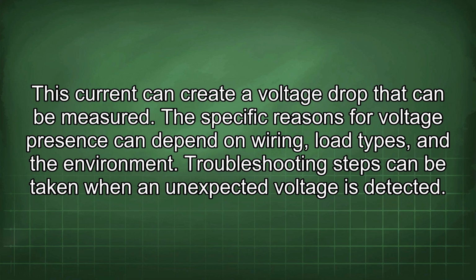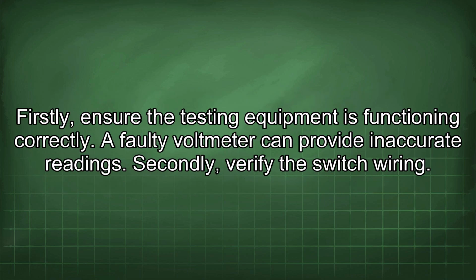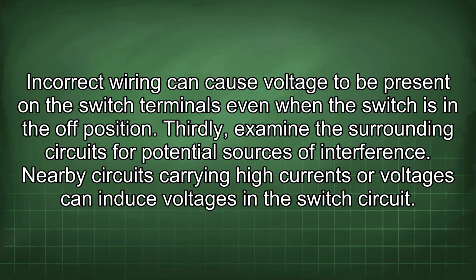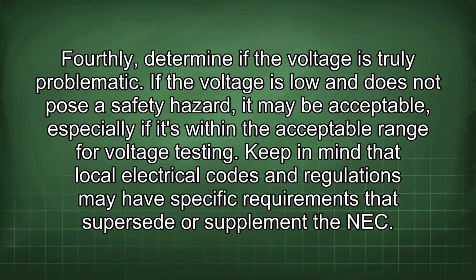Troubleshooting steps can be taken when an unexpected voltage is detected. Firstly, ensure the testing equipment is functioning correctly. A faulty voltmeter can provide inaccurate readings. Secondly, verify the switch wiring. Incorrect wiring can cause voltage to be present on the switch terminals even when the switch is in the off position. Thirdly, examine the surrounding circuits for potential sources of interference. Nearby circuits carrying high currents or voltages can induce voltages in the switch circuit. Fourthly, determine if the voltage is truly problematic. If the voltage is low and does not pose a safety hazard, it may be acceptable, especially if it's within the acceptable range for voltage testing.